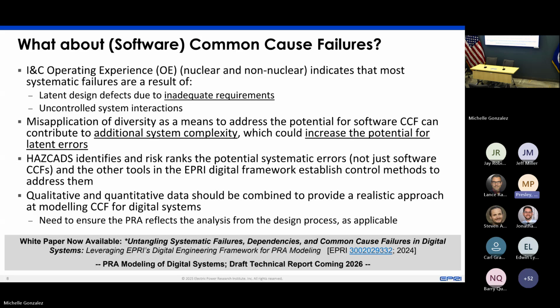the I&C operating experience - they looked at billions of hours of data outside of nuclear, as well as a thorough deep dive into nuclear experience, and found that the OE shows most systematic failures, or most potential common cause failures, are not like typos in the software. They're not those sorts of errors. They're typically latent design defects due to inadequate requirements or uncontrolled or ununderstood system interactions.